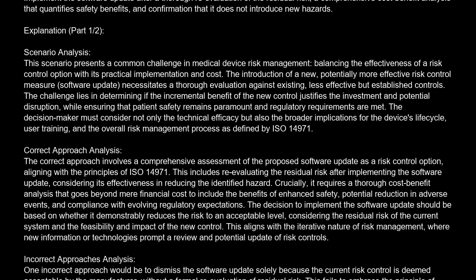The correct answer is C. Implement the software update after a thorough reevaluation of the residual risk, a comprehensive cost-benefit analysis that quantifies safety benefits, and confirmation that it does not introduce new hazards. Explanation. Scenario analysis. This scenario presents a common challenge in medical device risk management, balancing the effectiveness of a risk control option with its practical implementation and cost. The introduction of a new, potentially more effective risk control measure, a software update, necessitates a thorough evaluation against existing, less effective but established controls. The challenge lies in determining if the incremental benefit of the new control justifies the investment and potential disruption, while ensuring that patient safety remains paramount and regulatory requirements are met.